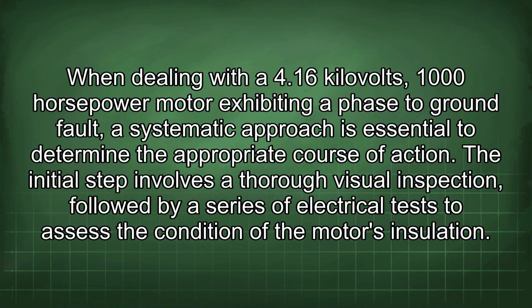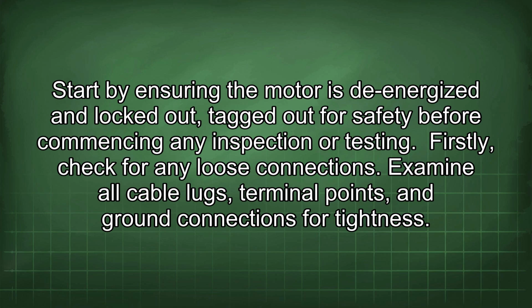When dealing with a 4.16 kilovolts, 1000 horsepower motor exhibiting a phase-to-ground fault, a systematic approach is essential to determine the appropriate course of action. The initial step involves a thorough visual inspection, followed by a series of electrical tests to assess the condition of the motor's insulation.